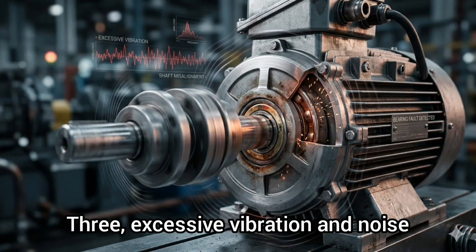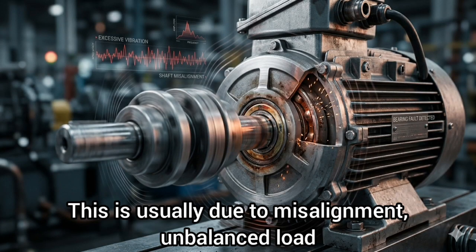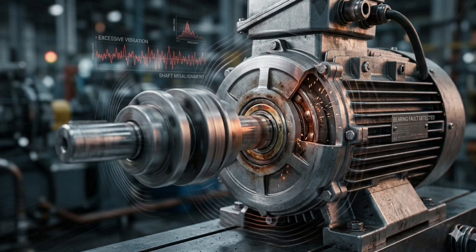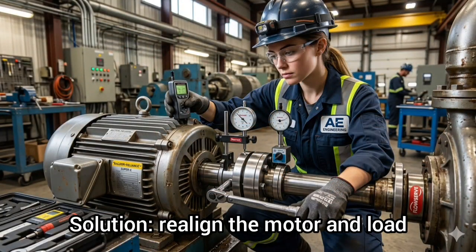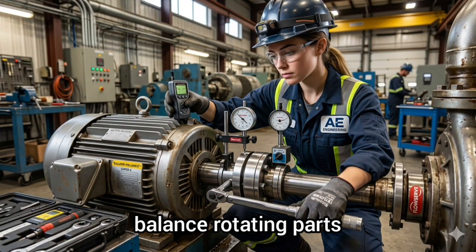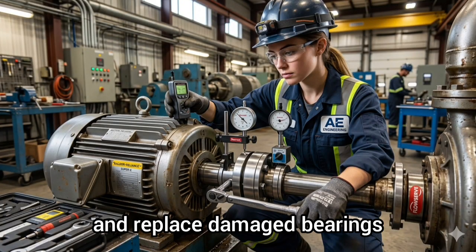3. Excessive vibration and noise. This is usually due to misalignment, unbalanced load, or worn-out bearings. Solution: realign the motor and load, balance rotating parts, and replace damaged bearings.